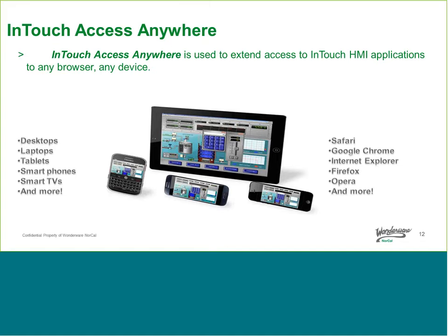We've got some great security behind this as well. If you have other questions about that, we can talk about that, but it includes what's called a secure gateway. It allows you to put the secure gateway in a DMZ. So when you want to access InTouch, you first have to go through a secure DMZ, which is not on the SCADA control network. Once you authenticate, the session launches InTouch from within your browser on the SCADA control network. So you're not actually accessing the SCADA control network directly from the public internet. You're actually going through a DMZ.